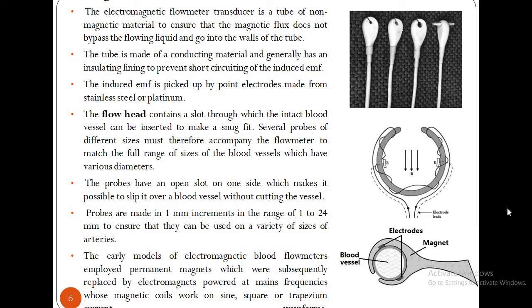In actual practice, the electromagnetic flow meter transducer is a tube of non-magnetic material to ensure that the magnetic flux does not bypass the flowing liquid and go into the walls of the tube. The tube is made of a conducting material and generally has an insulating lining to prevent short circuiting of the induced EMF. The induced EMF is picked up by point electrodes made from stainless steel or platinum. The flow head contains a slot through which the intact blood vessel can be inserted to make a snug fit. Several probes of different sizes must therefore accompany the flow meter to match the full range of sizes of the blood vessels, which have various diameters.